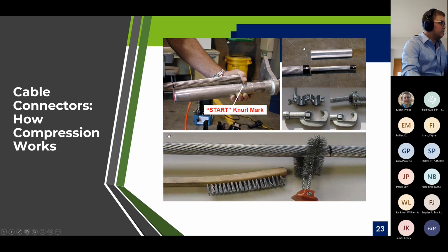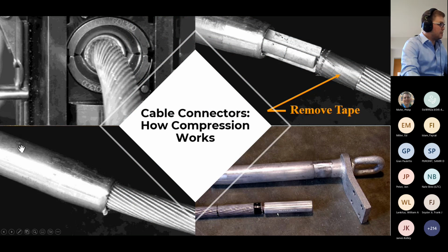Then we actually use some tools to cut and keep only the core, and we put this mold in there with it. And before we then put this into the barrel, we want to brush it to maximize the asperities and have the most uniform roughness, and make sure we minimize the amount of air gaps or water that will seep in. And in the next slide, we'll be able to show you, this is having the member now attached to the inner core piece, which then they'll start to push into the barrel.